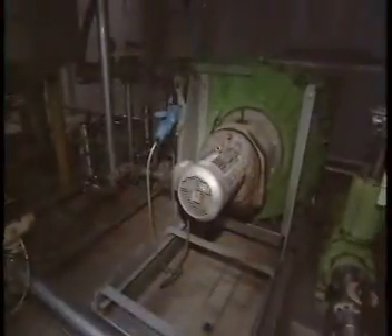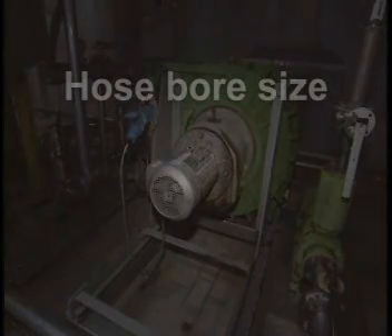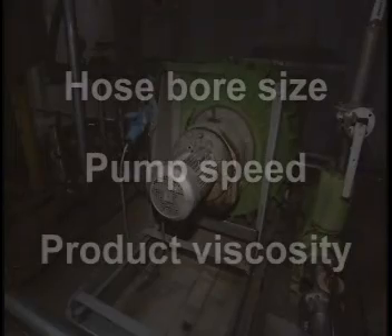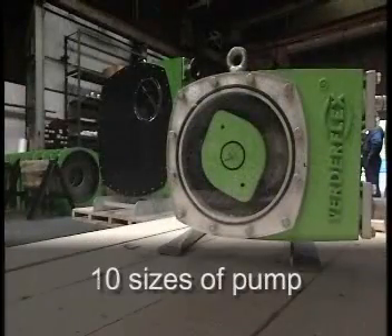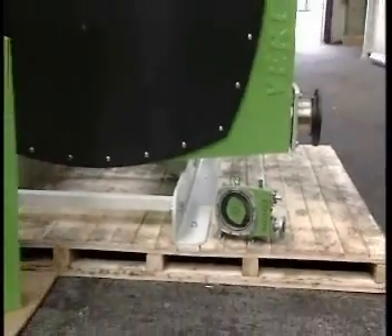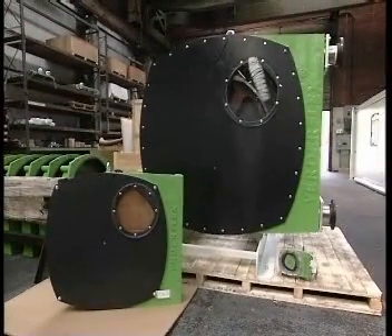The volume of product pumped is determined by factors such as the bore size of the hose, the speed at which the pump is run, and the product's viscosity. The Verderflex range includes 10 sizes of pump, each one defined by the internal diameter of its hose, ranging from 10 mm to 125 mm.